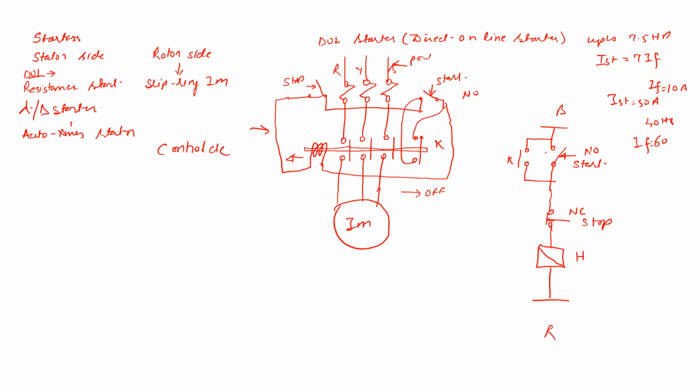Now see, we can understand this very well. As soon as we switch on the button, the current is going to flow through this conductor. It will energize the coil, and on energizing the coil, the plunger moves in this direction. So it will make the contact from here, and now the motor gets the supply. At the same time, this contactor also closes. So the current in the control circuit flows from the auxiliary contact to the stop button and to the holding coil to the next phase, isn't it? So the motor will remain on even though your start button is open.